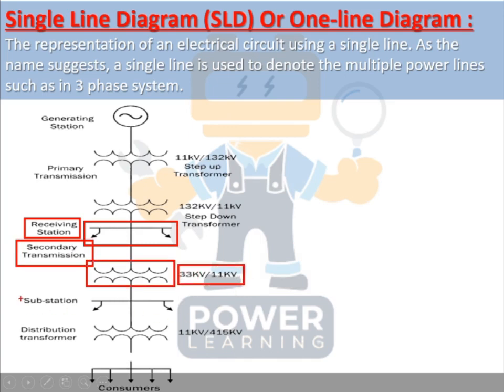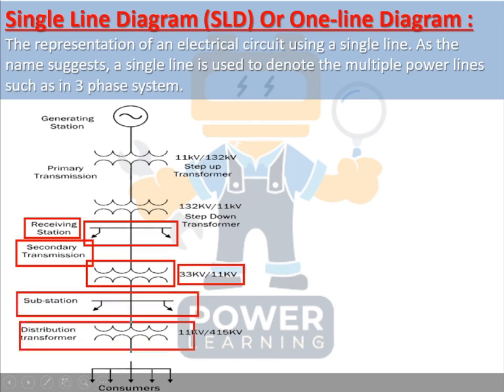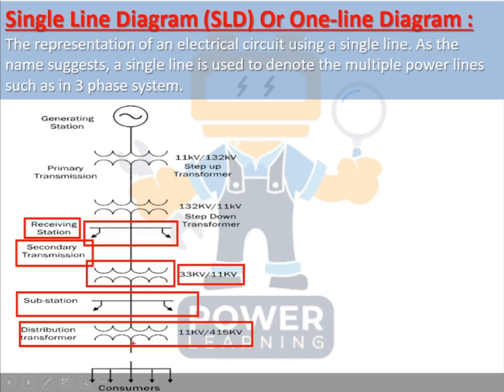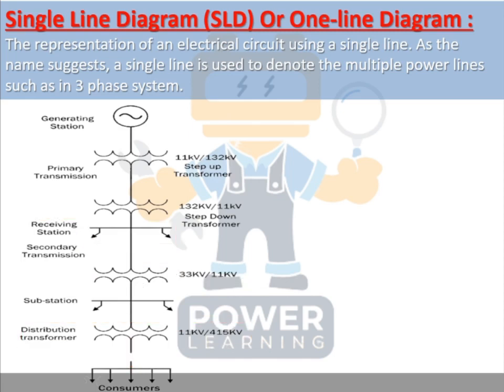After the receiving station, the system continues to secondary transmission with another transformer stepping down from 33 kV to 11 kV, followed by another substation. Then we have a distribution transformer stepping down from 11 kV to 415 V. The final single line shows the transmission between the customer and the distribution transformer — the whole network is represented on one single diagram.